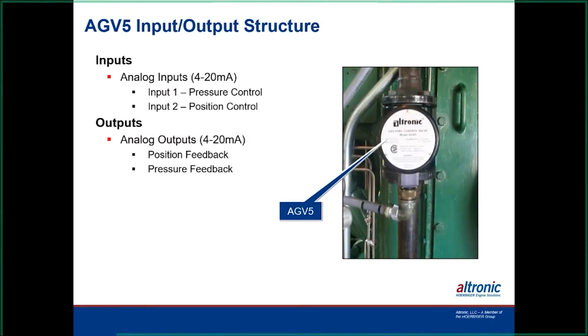We're also adding the cannon plug to it now. This is the only way you can buy the valve if it's new, because what's been happening in the past is people take the cover off and move the computer board inside of it, and it throws off the calibration on the output positioner. So it has to be sent back to the factory or to some of the distributors to be recalibrated. This will come with the valve now if you order any new valves. It makes it a lot cleaner if you need to replace it or send it in for service than getting inside of it and disconnecting the wires.